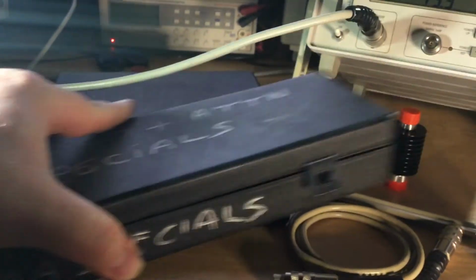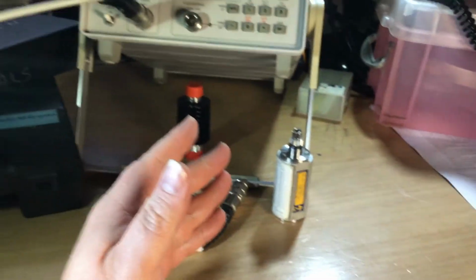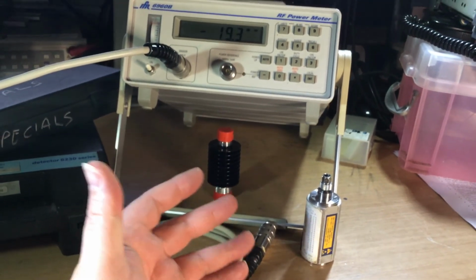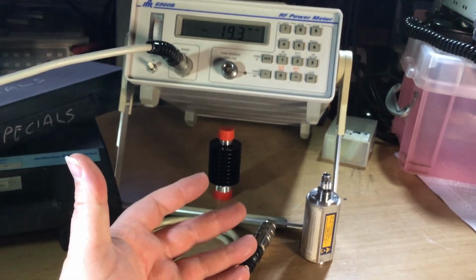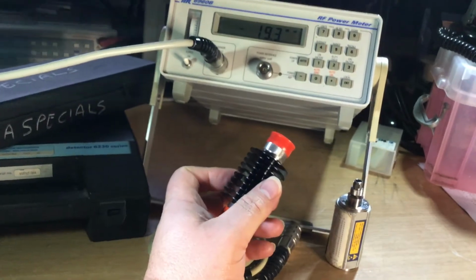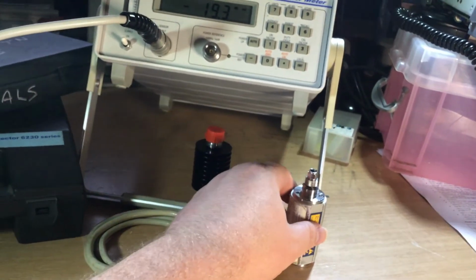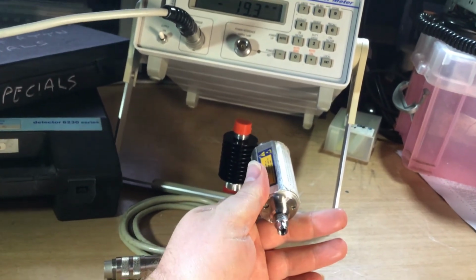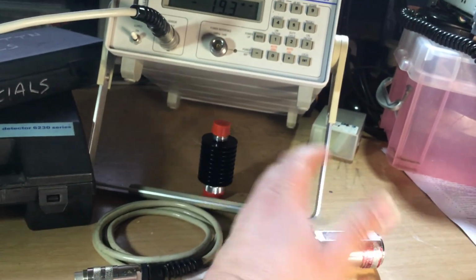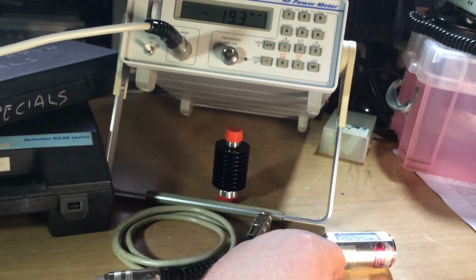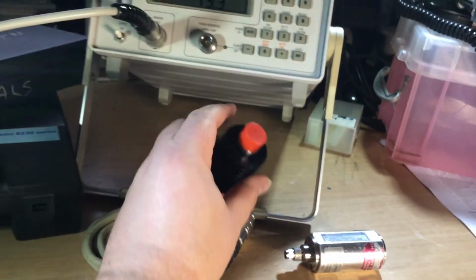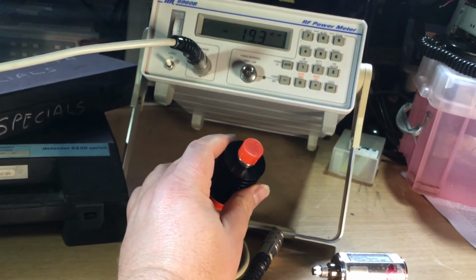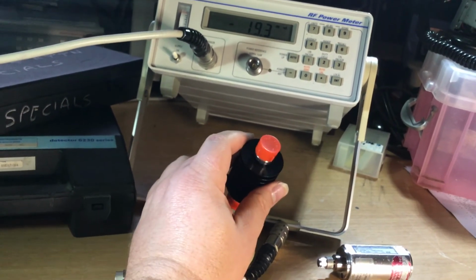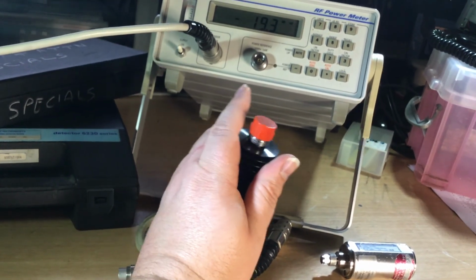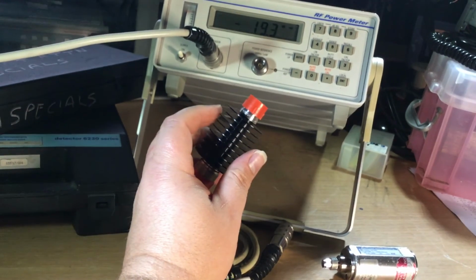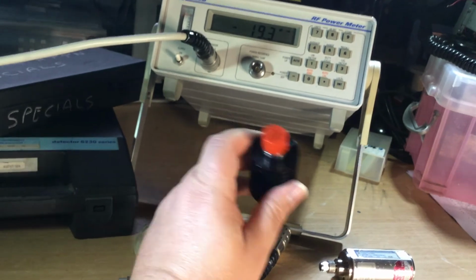So the biggest problem with these power meters, to avoid damage, is if you don't know what level of attenuation you need when making an RF measurement, then that's when you risk the most damage. Because if you're measuring a 50-watt transmitter, for example, and you've not chosen the right RF attenuator, if the RF level coming into this sensor exceeds 100 milliwatts, then you'll damage the RF sensor. So what I would advise, if you use an external attenuator, is to get a known RF power meter, a proper Bird through-line meter or something like that, and connect it to the output of the attenuator before you connect the sensor, and just make sure you're reading less than 0.1 of a watt on it. It'll barely move the needle on a Bird through-line meter. If that's the case, then you know that when you connect the sensor to the attenuator it won't damage the sensor.